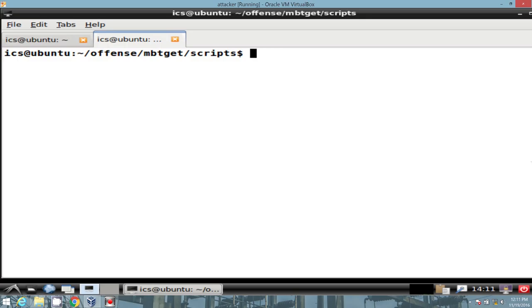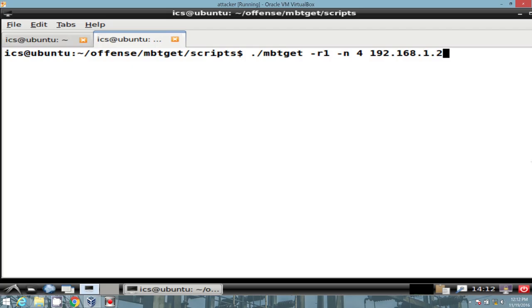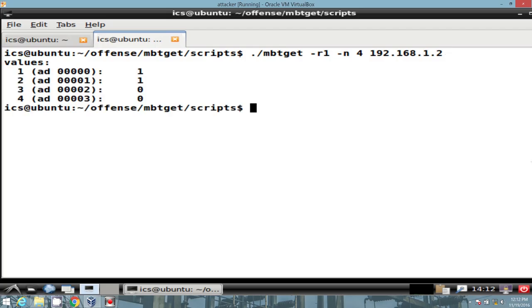So what we're going to do now is actually start issuing a few of the function codes to different devices to see what will happen. I'm going to specify a function code 1 read coil 1-bit status, I want to see four addresses, and we're going to go ahead and use that web switch. And we see that address 0 and address 1 both have a value, a coil value of 1-bit, meaning they're both on.